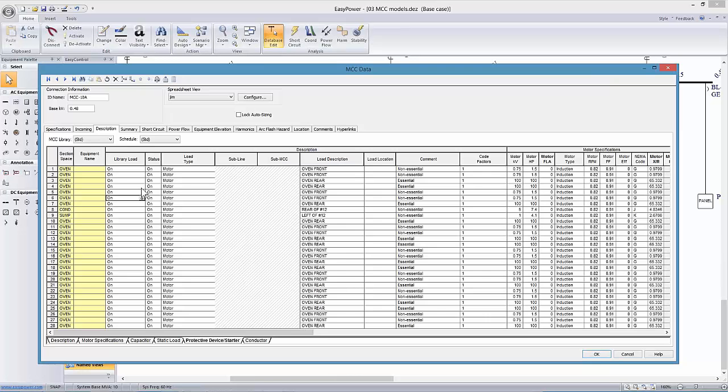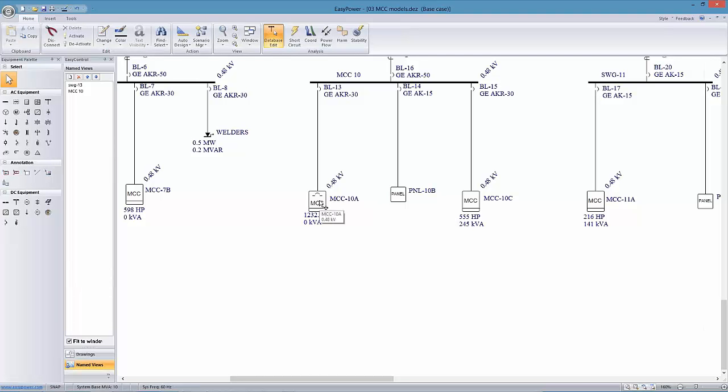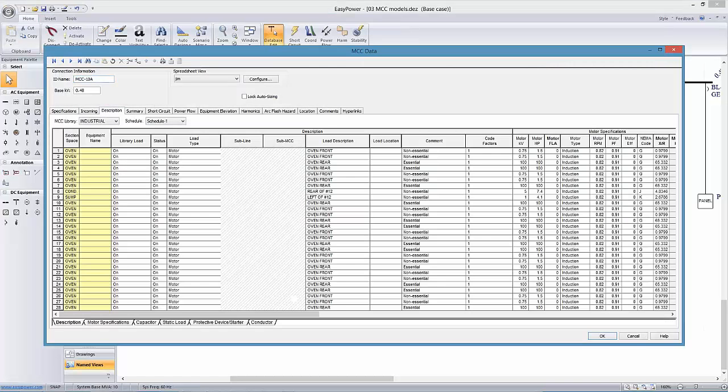Okay, so not to get sucked into the well of Excel, I want to make one other point here that's available for MCCs, and that is the ability to do library load. As I select what's essentially a customized setup sheet that I've built, I'm going to designate or connect that, and as I close the MCC and then reopen it, it makes it available to me to pick up under library load. So let's go downstream.